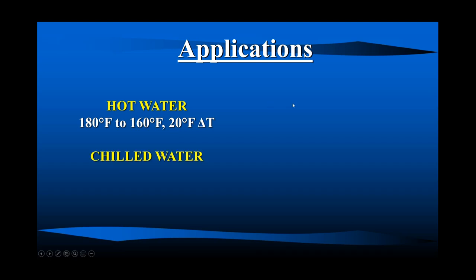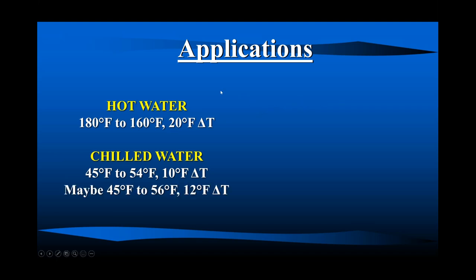Chilled water, 45 to 54, 10 degree delta T system. That's staying the same, although 10 degrees will probably move a little bit higher. 45 to 56, 12 degrees, all in the order of decreasing pumping power and maybe making a smaller pipe size if we can on that system. So hot water and chilled water.